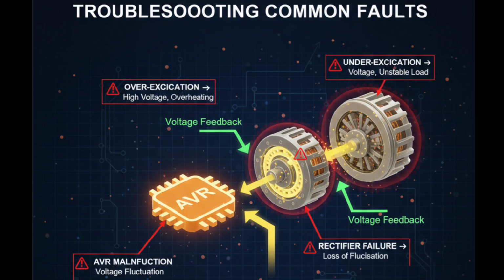Troubleshooting common faults. This slide focuses on troubleshooting, a key area for practical marine engineering and exams. Notice the 3D graphics highlighting the rotor, rectifier, and AVR, with red warning icons representing faults. Common faults include: 1. Over-excitation, high voltage caused by AVR failure or control wiring issues. It can lead to rotor overheating and insulation damage.